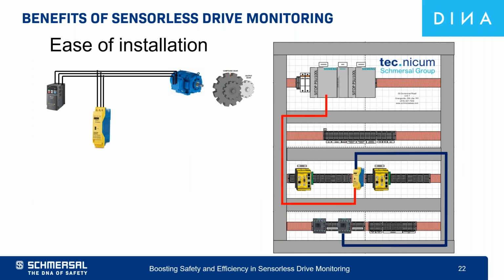Another great reason to use sensorless drive monitoring is the ease of installation. They're mounted typically inside the same panel where all the motor wiring already exists. So there's no reason to go out in the field and install sensors or encoders and run the wires back to those devices in the panel. So, huge time savings.